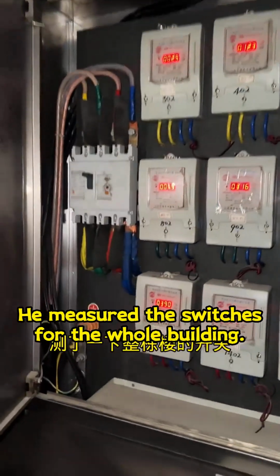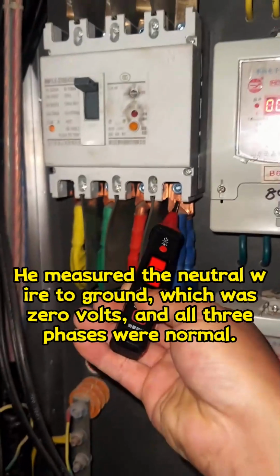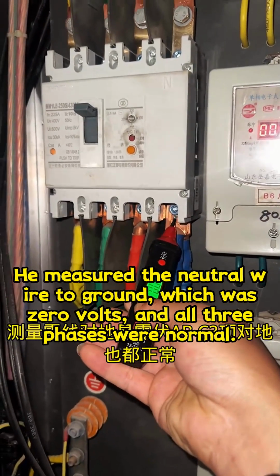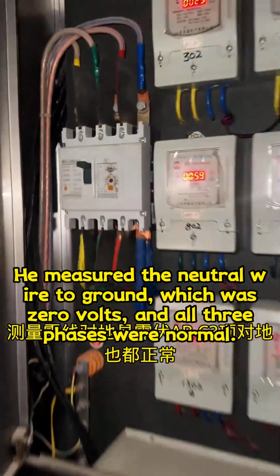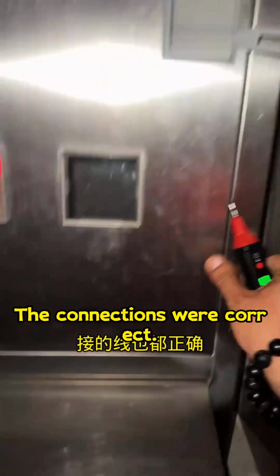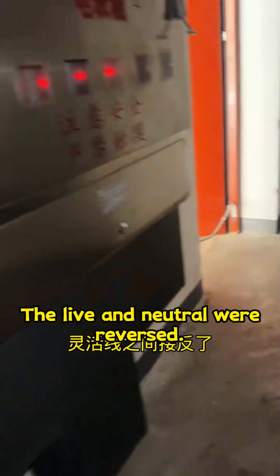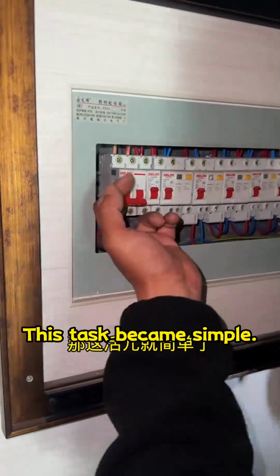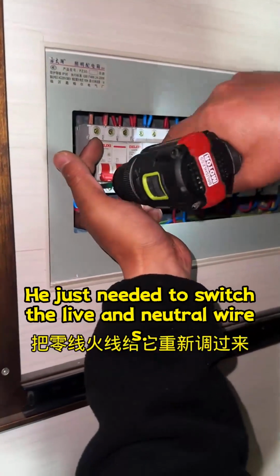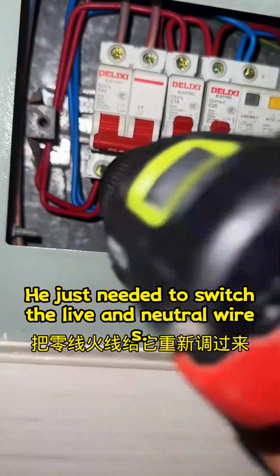He measured the switches for the whole building. He measured the neutral wire to ground, which was 0 volts, and all 3 phases were normal. There were no issues with the downstairs circuit. The connections were correct. It was due to his own wiring. The live and neutral were reversed. This task became simple. He just needed to switch the live and neutral wires.